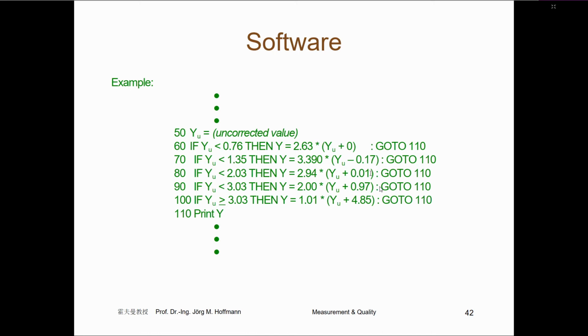That means this program is the guideline for the computer, how to calculate from these uncorrected values the true value in centimeters. And that for every point on the sensor, because you get for every point a voltage, and you go in the program and look where you are, in which line you are, and then you calculate with the right calibration constant.